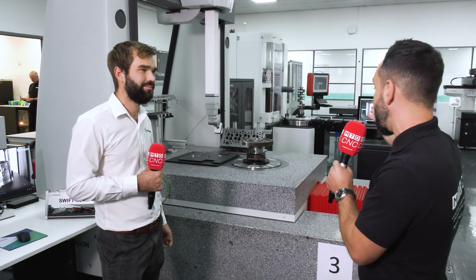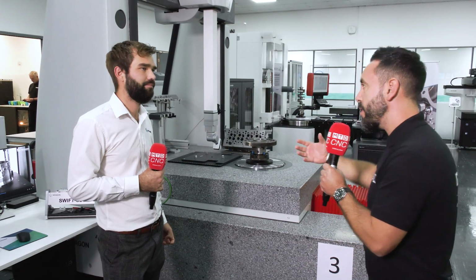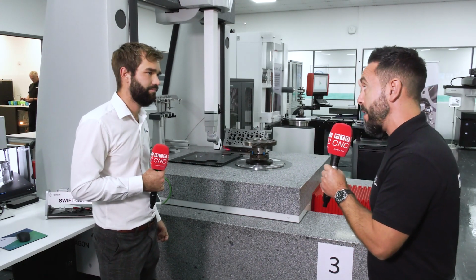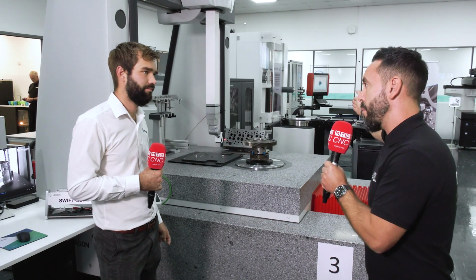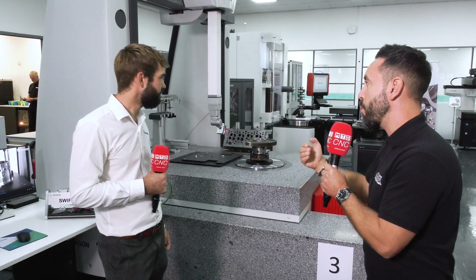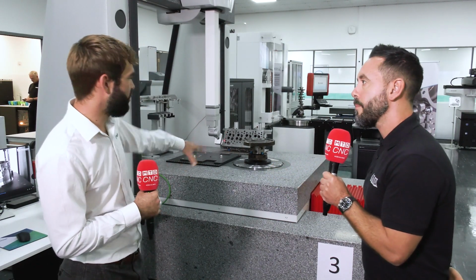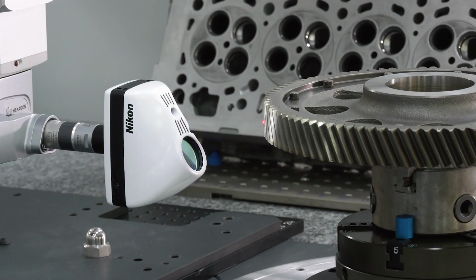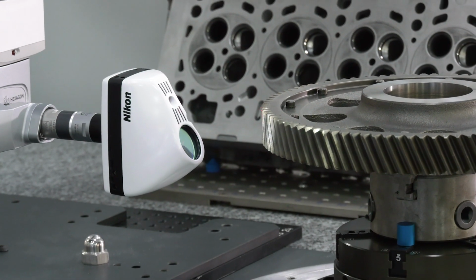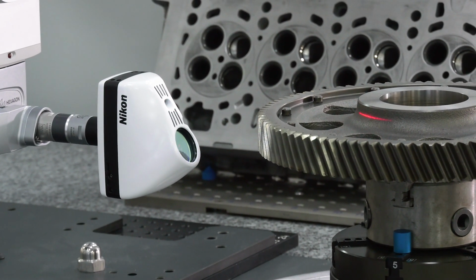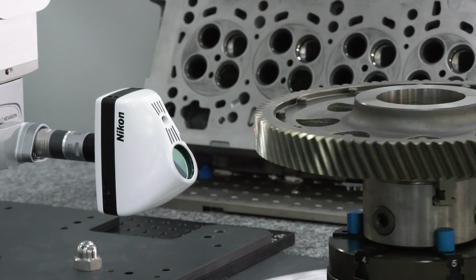You have a second machine further behind us. Can you explain the differences between the horizontal probe and the vertical probe and why this is configured in a different way? Yeah. So this machine here is configured to be your absolute point of accuracy in the system. We're looking at final inspection, are the parts absolutely right? If there's something wrong, what's wrong? This is the investigation machine and the foolproof of your process and validation.